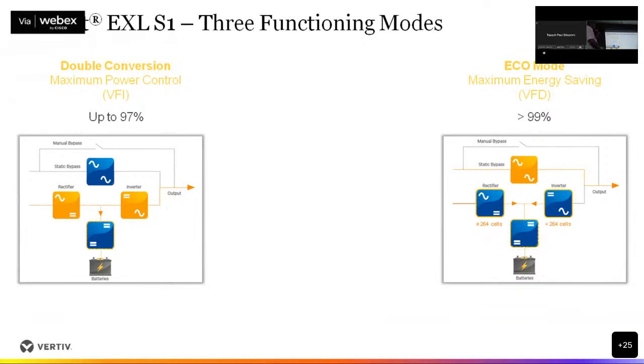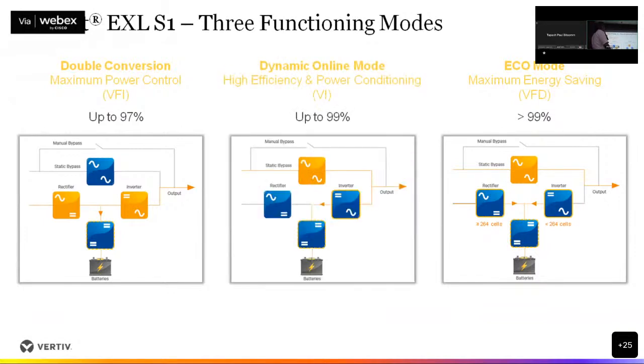In this whole exercise, you are losing 3% of energy, obviously due to the AC to DC and DC to AC operation. What we have come up with is a new technology, a combination of double conversion in eco mode. We call it dynamic online mode, and in technical terms it is VI mode. It is the differentiation factor here. Although the load is protected through your static bypass, the inverter is always kept on.